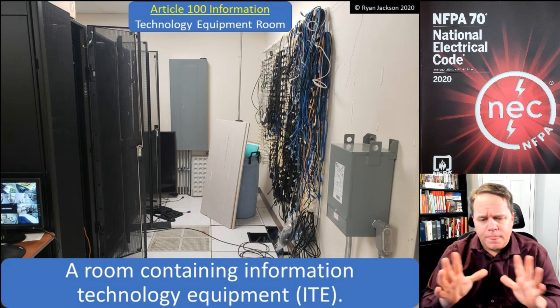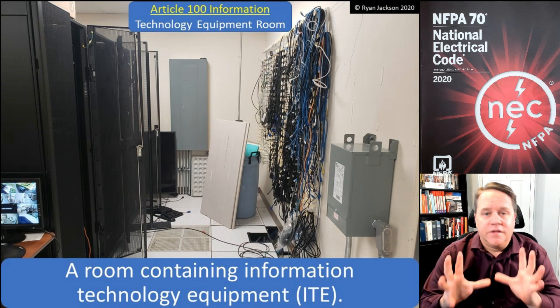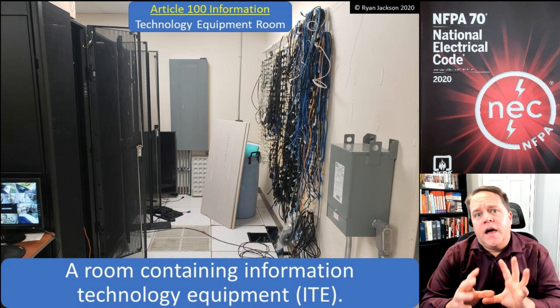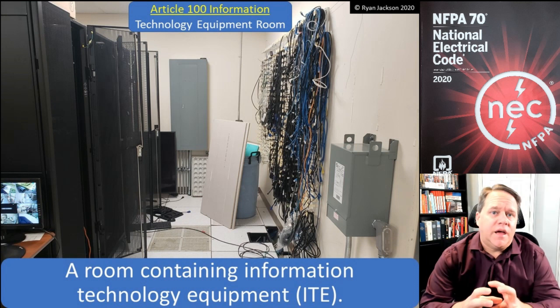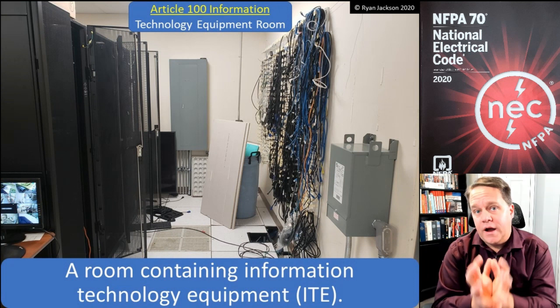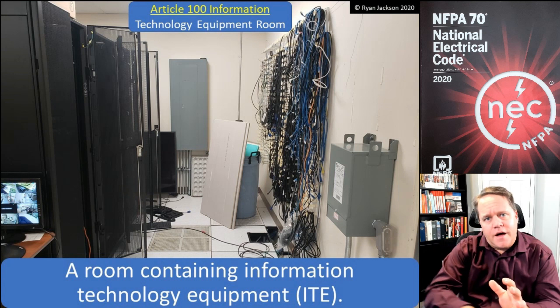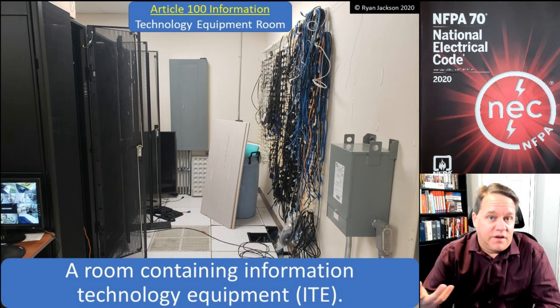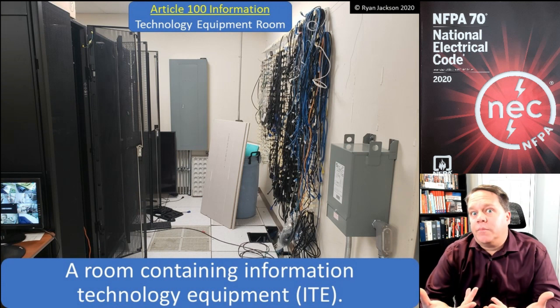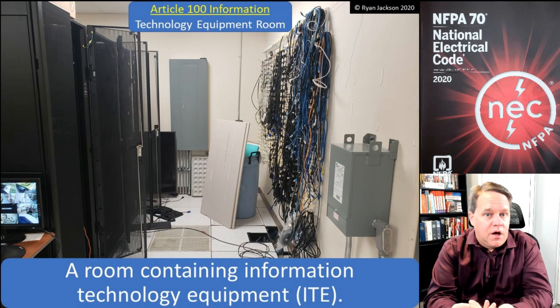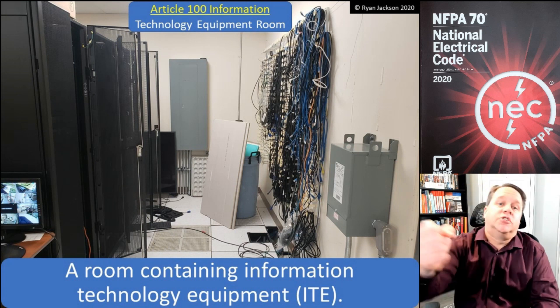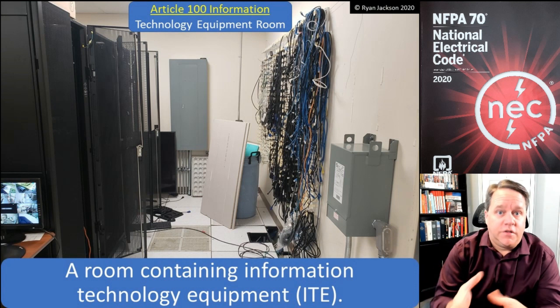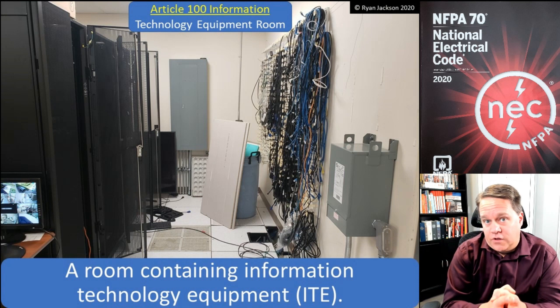They figured out that if you have an IT room dedicated just to equipment — with no people in there on a regular basis — and the HVAC system is dedicated solely to that IT room with its own air handling system, then if non-plenum rated cables under that floor produced toxic gas in a fire, it's probably not a huge deal because nobody is in that room. But first responders need a way to shut off the air handling system and all the equipment in the room.